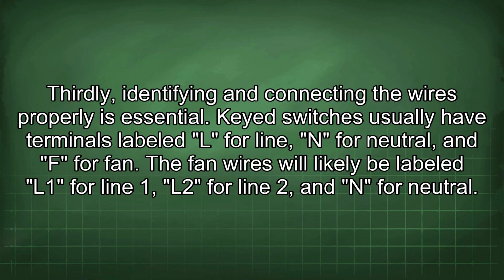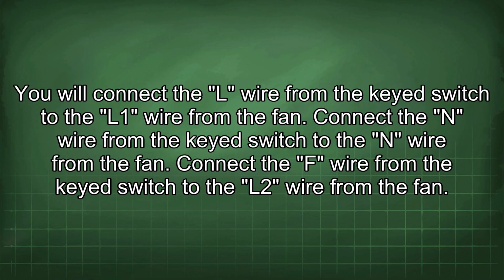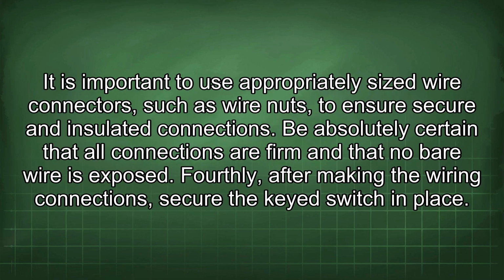Identifying and connecting the wires properly is essential. Keyed switches usually have terminals labeled L for line, N for neutral, and F for fan. The fan wires will likely be labeled L1 for line 1, L2 for line 2, and N for neutral. Connect the L wire from the keyed switch to the L1 wire from the fan, connect the N wire from the keyed switch to the N wire from the fan, and connect the F wire from the keyed switch to the L2 wire from the fan. Use appropriately sized wire connectors, such as wire nuts, to ensure secure and insulated connections. Be absolutely certain that all connections are firm and that no bare wire is exposed.